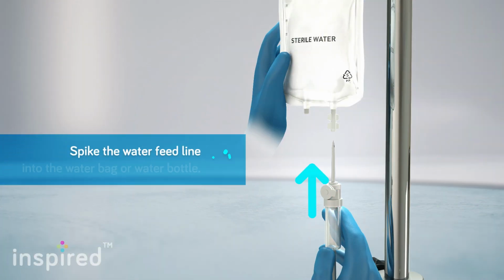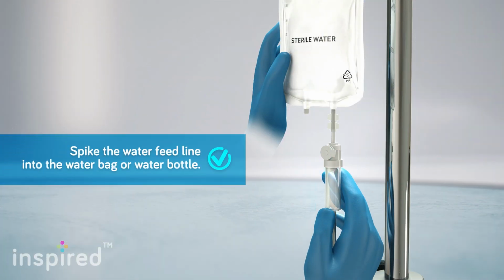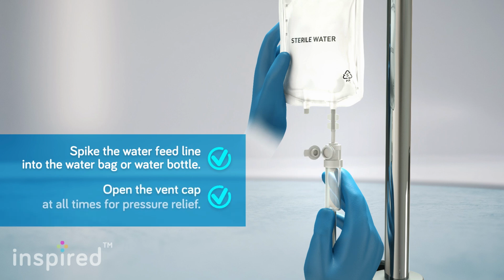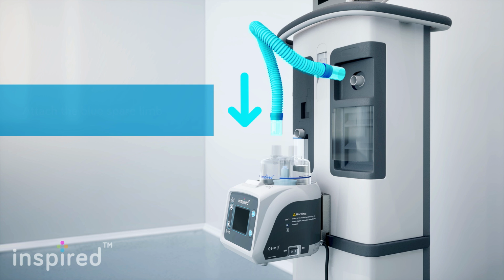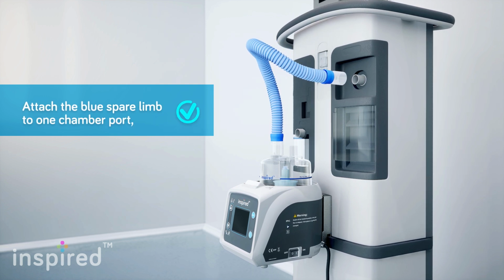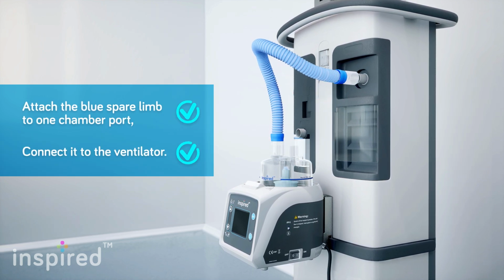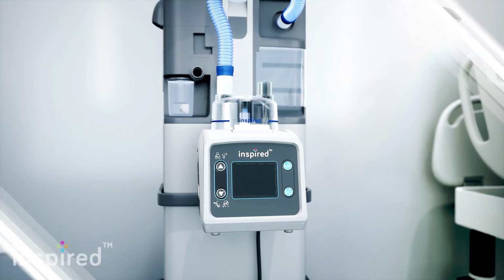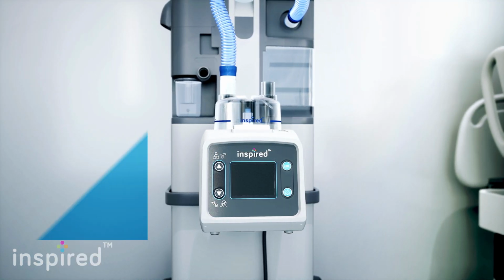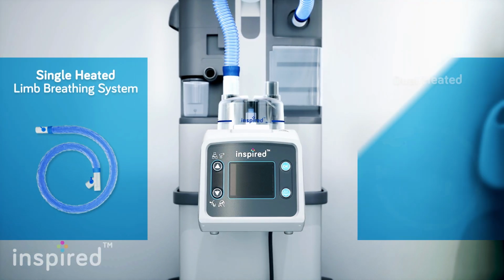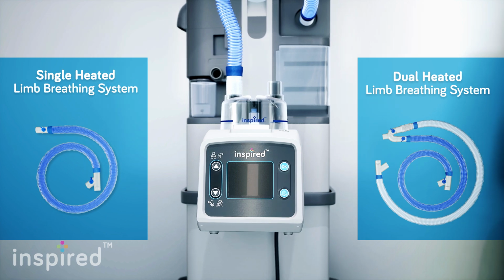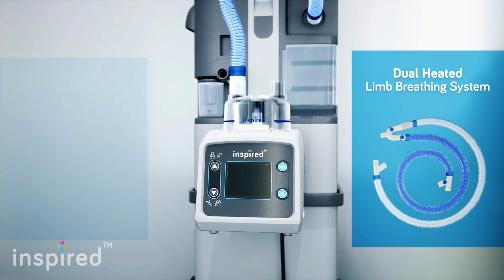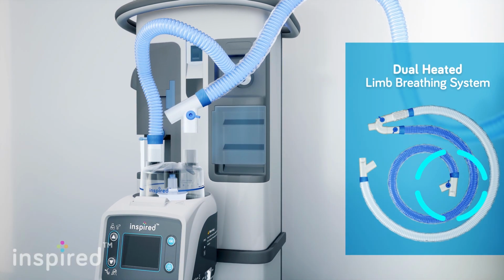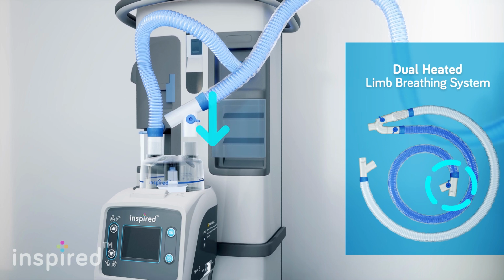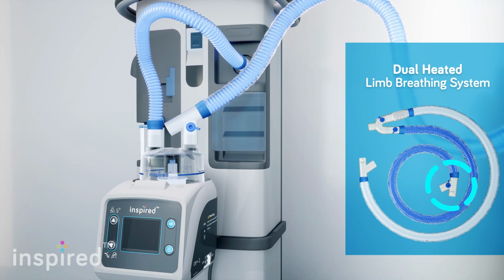Spike the water feed line into the water bag or water bottle. Open the vent cap at all times for pressure relief. Attach the blue spare limb to one chamber port and connect it to the ventilator. VHB can support single heated limb breathing system or dual heated limb breathing system. For dual heater wire circuit, attach the inspiratory limb to the chamber port.